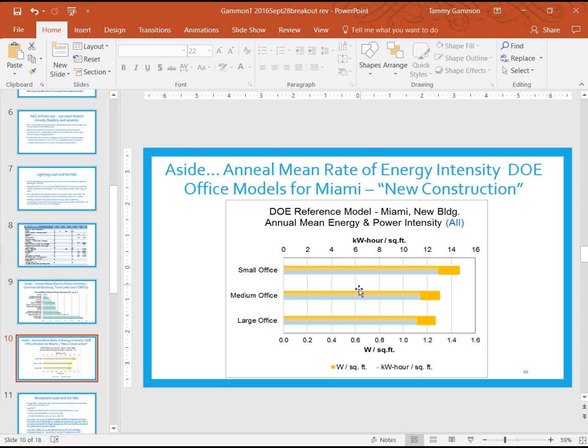If I look at a small office, the watts per square foot in yellow is about 1.5 watts per square foot. That's an annual mean. According to the NEC, we're designing at 3 watts per square foot. So I'm inviting feedback, because I find it mind-boggling that our annual mean loads are so low compared to what we design for one component of the total building load.